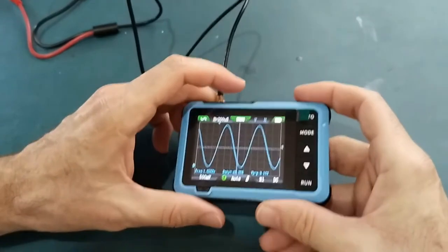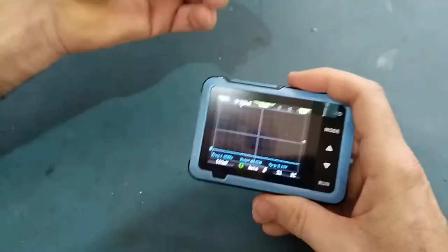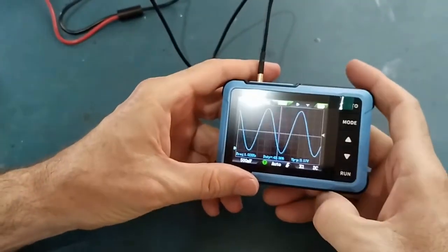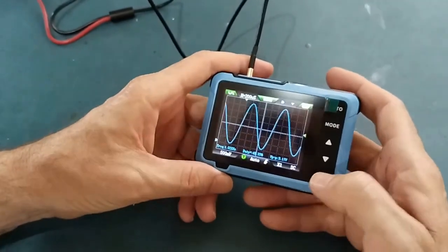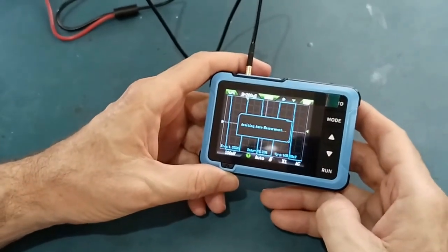There are longer videos and the user manual that demonstrate how to navigate the menu system. Here I've already connected a wave generator and I'll press auto for it to calibrate itself. Auto. There you can see, it gives me 3 volts peak to peak and 1 kilohertz.